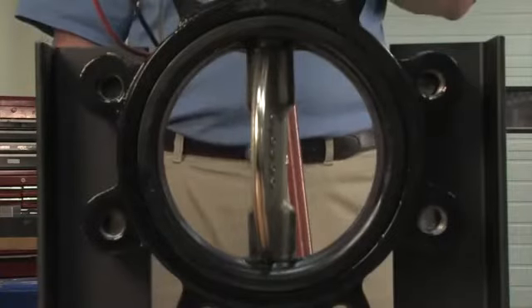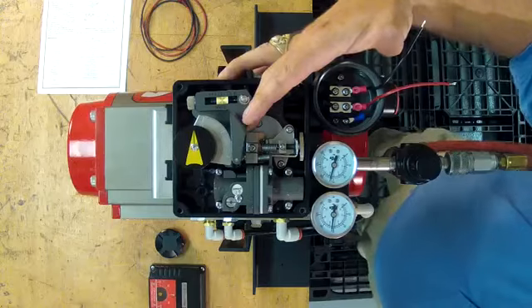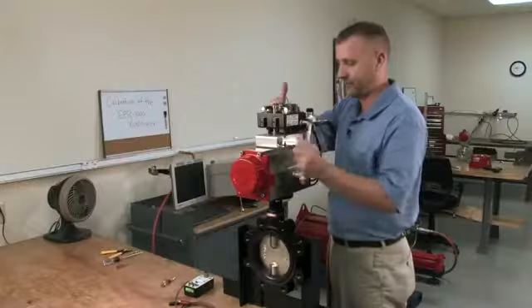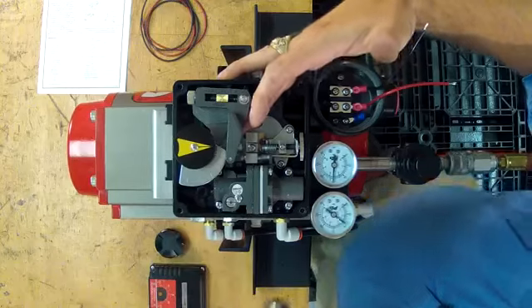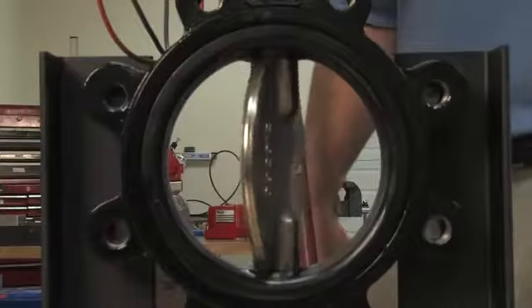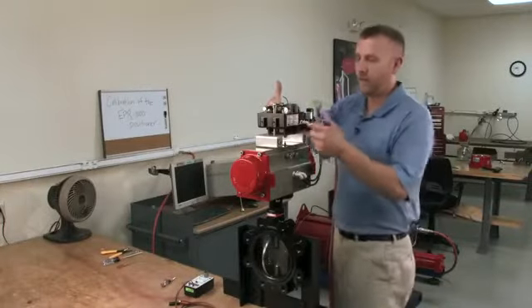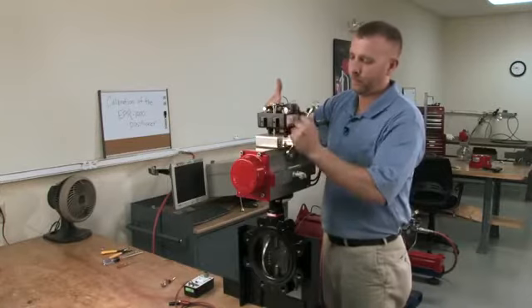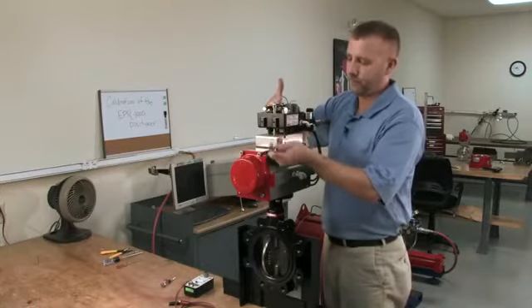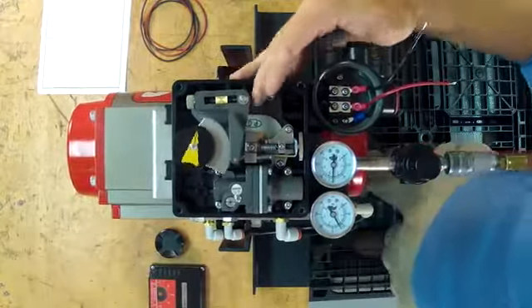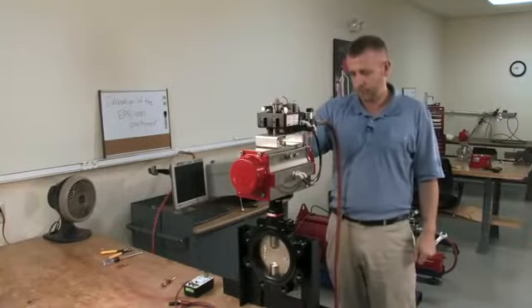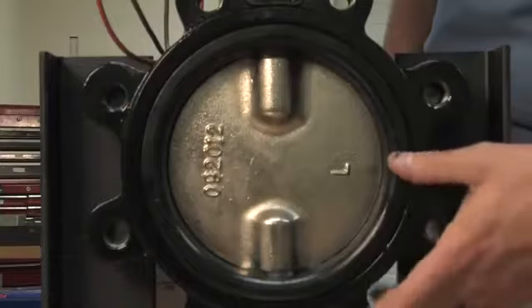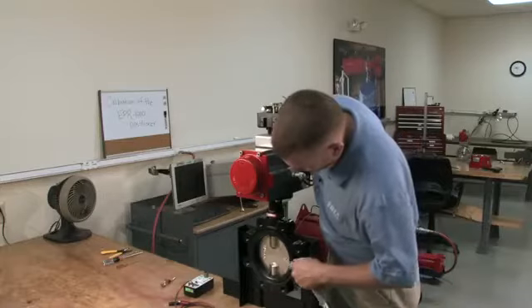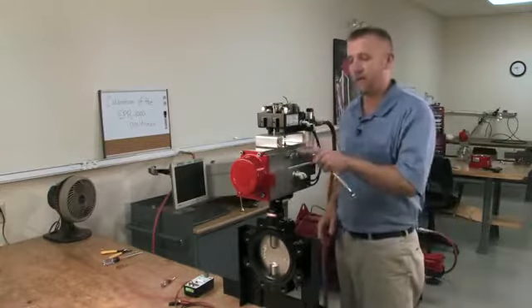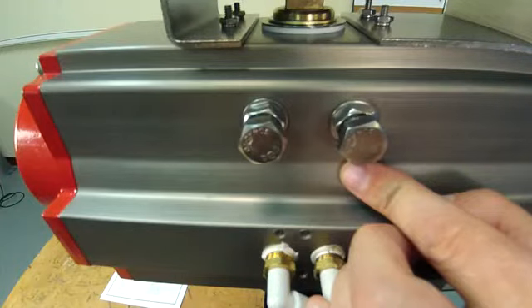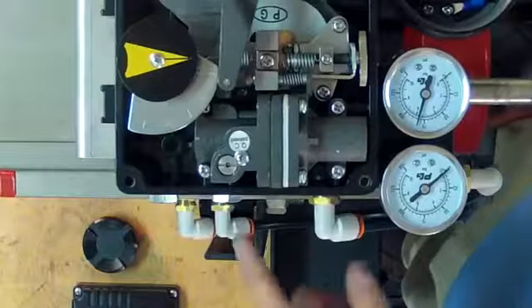As you see, that is not parallel, so we will back our open stop off a turn or two. That looks good. Now leave it open. Lock our stop down. Clockwise stop works the same way. You're looking for a nice even seat in the valve, which just looks fine. If not, same theory with the closed stop. You have a +5 or -5 adjustment on your stop, and adjust the same way.